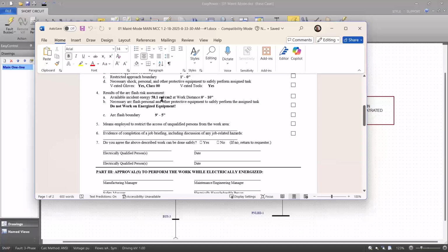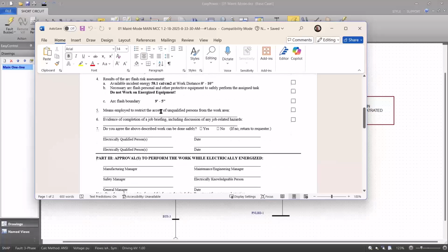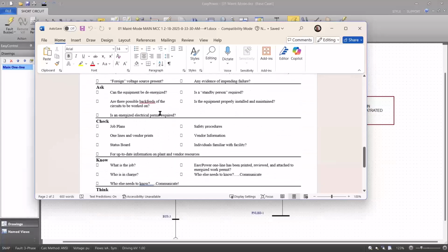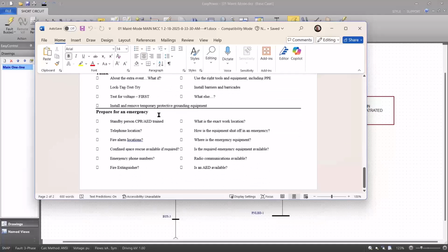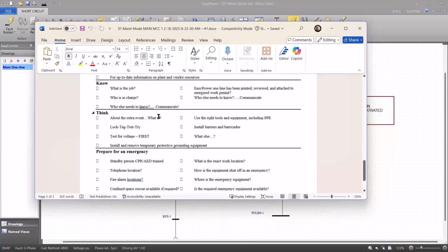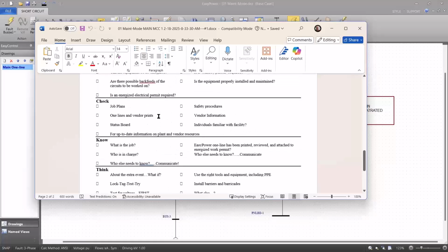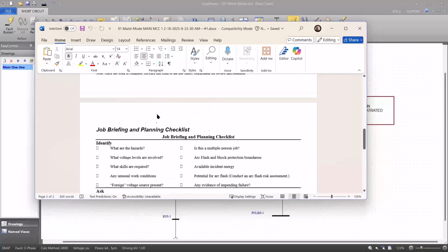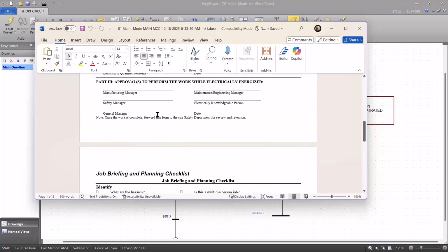And that's why this information in maintenance mode would be required on the work permit, not on the label, in my opinion. It describes the work, describes the safety procedures, and it has a place for management to sign off with an understanding that personnel have been placed in an elevated hazard situation and management is aware of it. So again, these are built in, and once they're set up, they can be used to create a hard copy of the work permit.